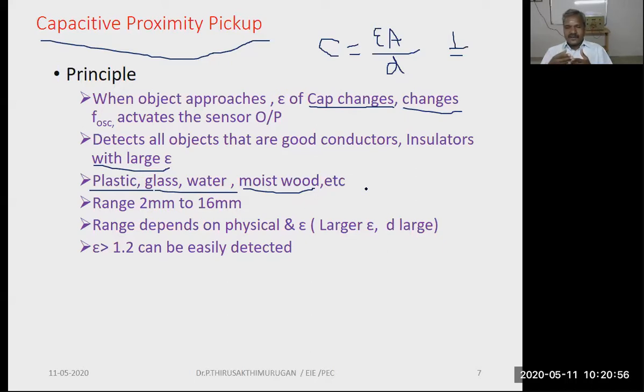Similarly, you can also detect quartz type of materials, because quartz has a dielectric constant value of 3.5. So the capacitive proximity pickup ranges from 2 mm to 16 mm. Actually, the range depends on the physical construction of the sensor, the physical size of the material, as well as the dielectric constant of the material. So depending on the dielectric constant and the physical structure of the object, the range can be extended or decreased. Dielectric constants more than 1.2 can be easily detected by this type of proximity pickup.